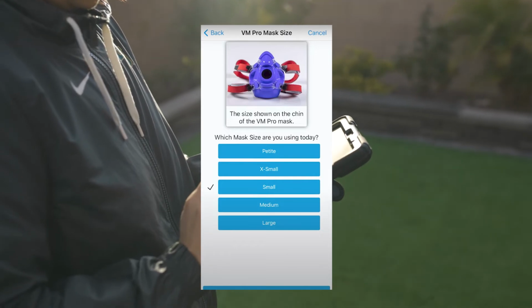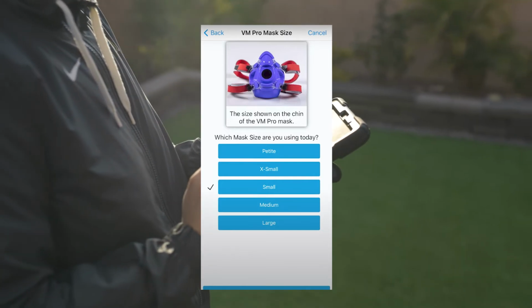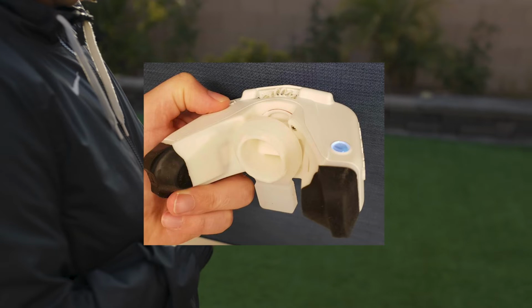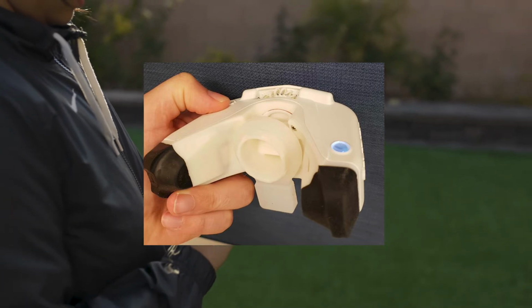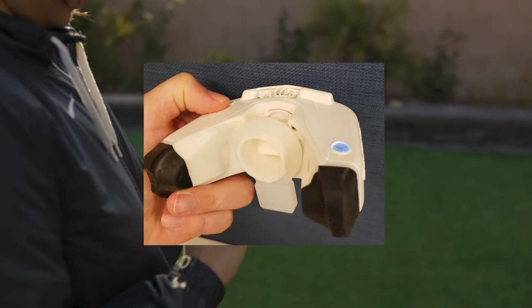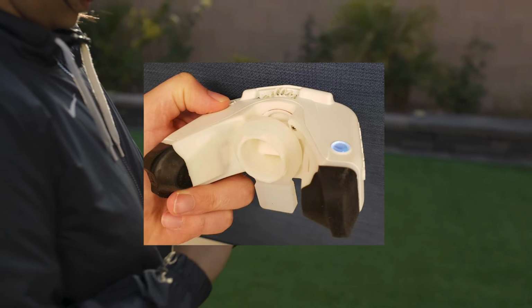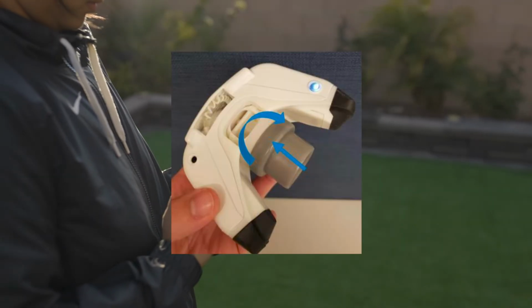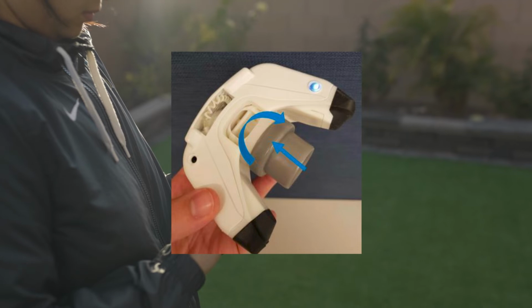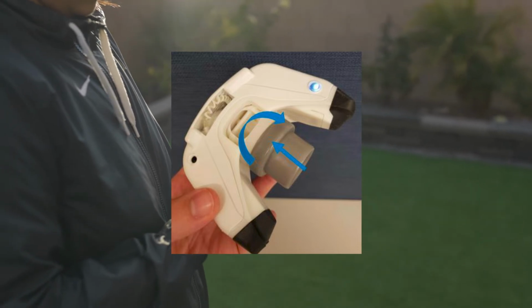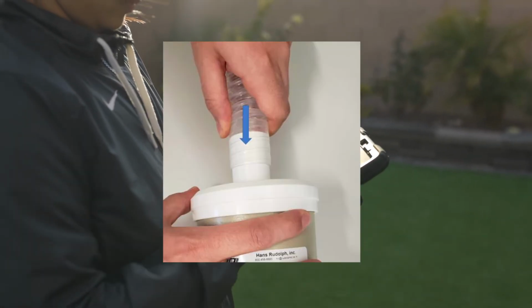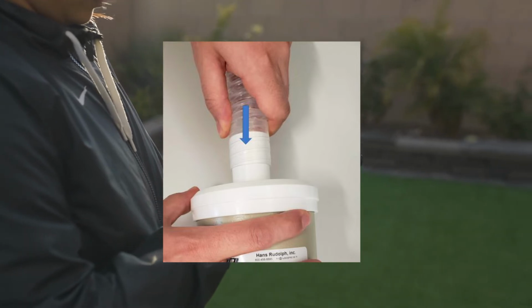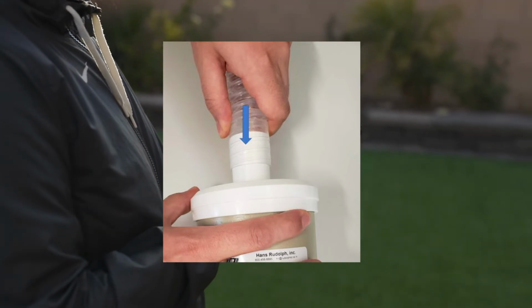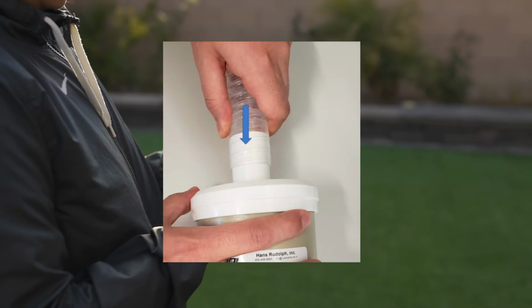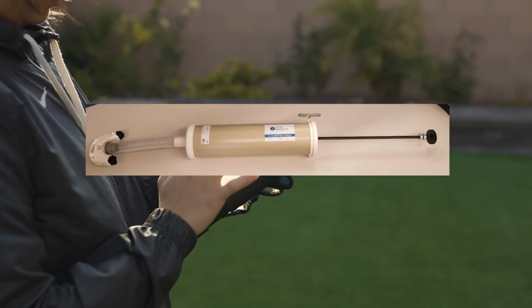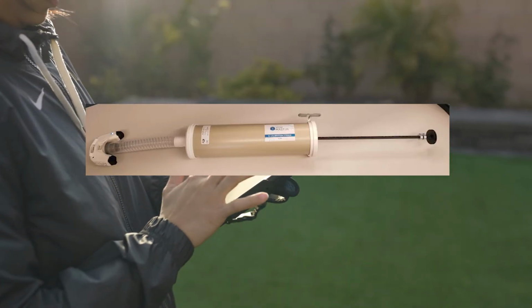First, you're going to calibrate the VO2 Master Analyzer for flow. With the filter inserted and chosen user piece in place, slide the silicone seal onto the user piece with the square end facing towards the top of the device. Next, attach the user piece adapter to the user piece by aligning the grooves and twisting it clockwise. Now, place the shock dampening hose onto the 3-liter calibration syringe by gripping it close to the end. Slide the user piece adapter into the shock dampening hose just like so.